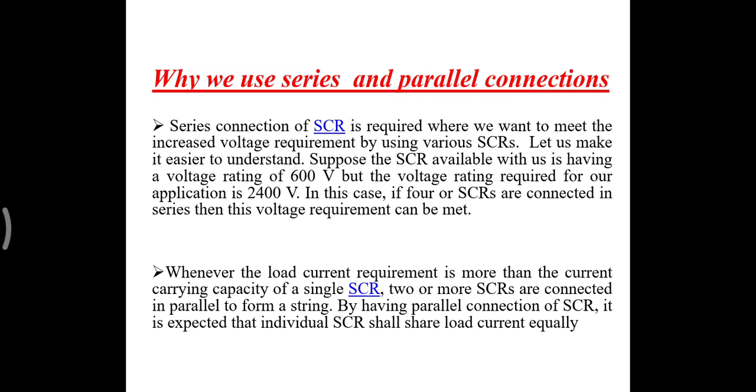That means suppose we have a load voltage of 2400 volts, but we have an SCR with a rating of only 600 volts. In that situation we have to connect 4 SCRs in series to reach our required voltage. So this is the main purpose of the series connection.